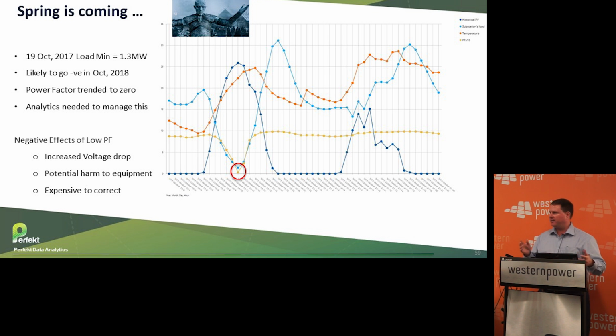That gets into the data cleansing problem and being able to handle what happens. So negative effects of low power factor: increased voltage drop is a big one if you've got long lines, potential harm to equipment, particularly older equipment without good power factor correction, and it's actually expensive to correct.